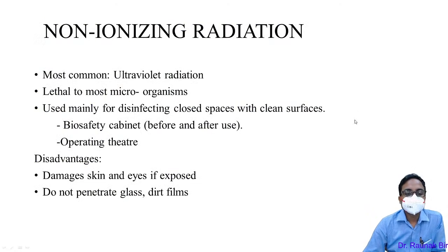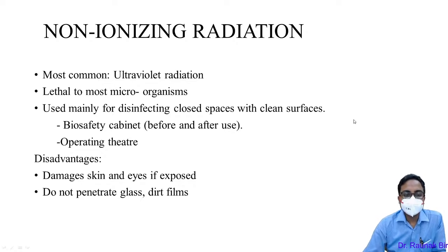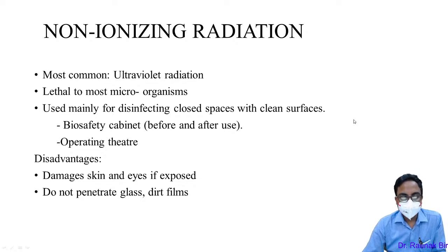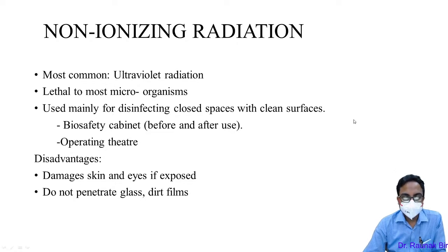Non-ionizing radiation uses ultraviolet radiation, which is mostly lethal to microorganisms. It mainly causes disinfection on closed clean surfaces and has less penetrative power. Most commonly used in biosafety cabinets where regular cultures are performed, creating a sterile environment after UV radiation exposure for a designated time period and dose. Disadvantage: it can damage the eye and skin on direct contact, and it does not penetrate dust, proteinaceous materials, or glass.